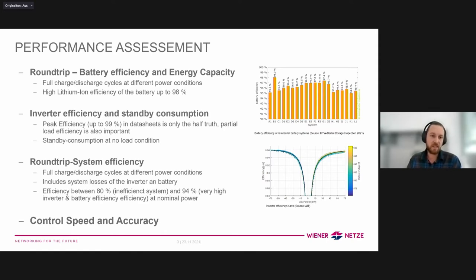The next test is the inverter efficiency and standby consumption. When you connect the battery to your connection point at the grid, you need the inverter. For this, we usually generate efficiency charts like this one on the bottom right. Here you can see the efficiency for discharging is quite high at nominal power, but lower when the discharge or charging power is lower.